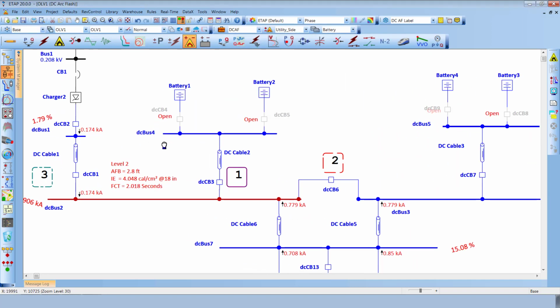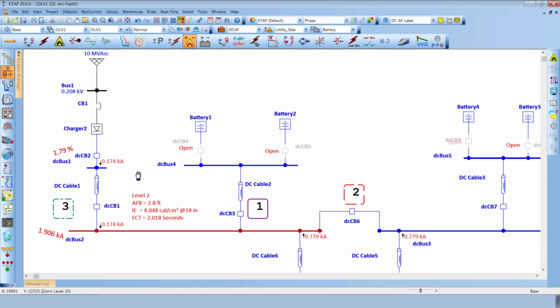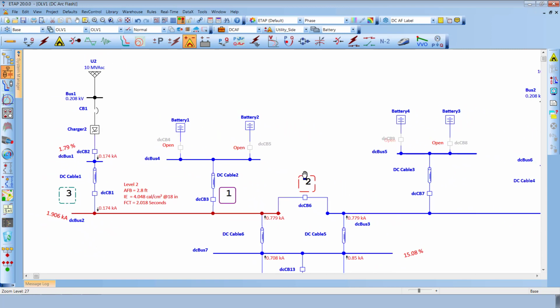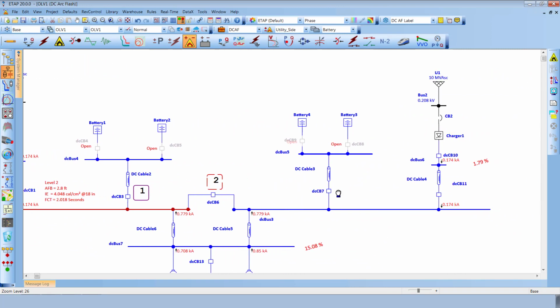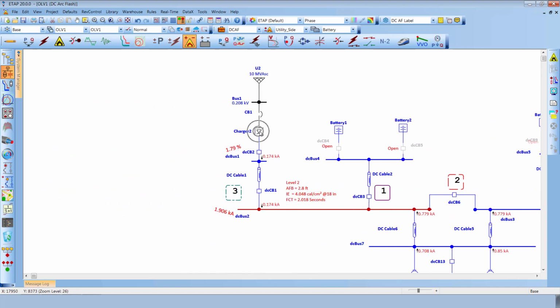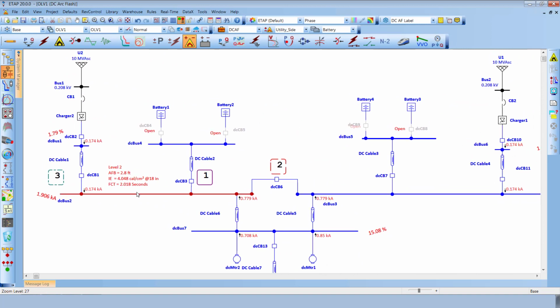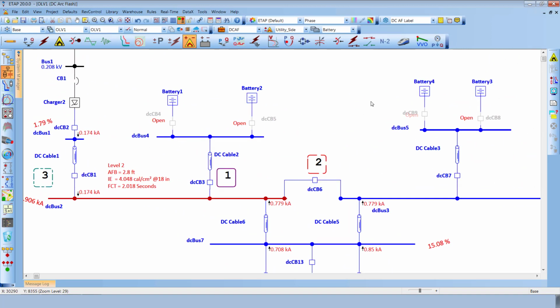To begin with, I have created 3 different scenarios based on the different configurations that I just explained and evaluate the incident energy based on each configuration. So scenario number 1 explains the incident energy calculation based on the contribution of the utility and the chargers only. So we do have 2 charger contributions, one from the charger 1 on the utility U1 and the charger 2 from the utility U2, based on the fact that the batteries are out of service, or in other words, in charging mode.